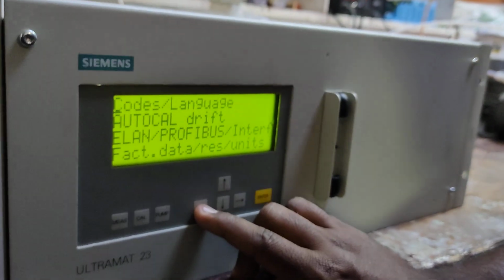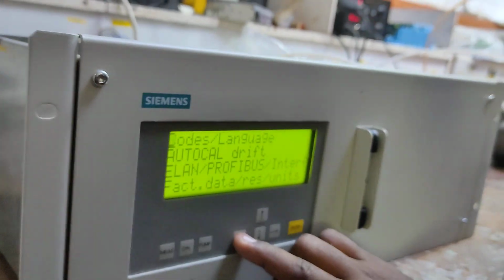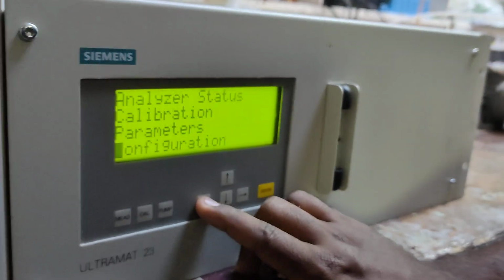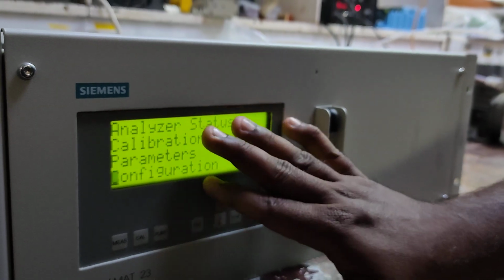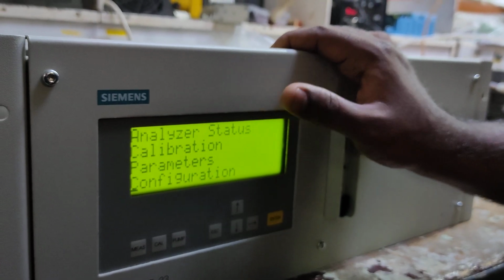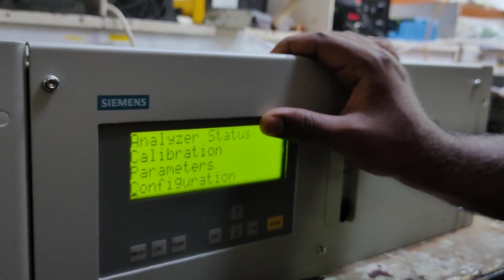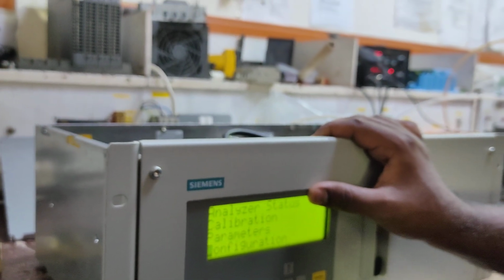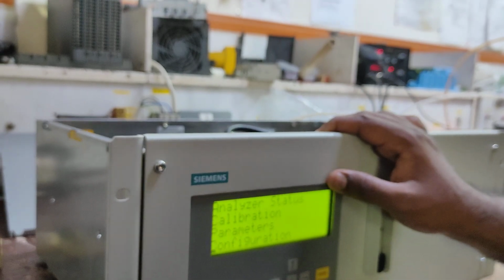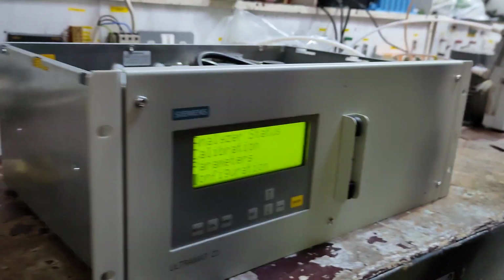A lot of alarms are there. All the alarms are in the manual. But what I am showing is your day-to-day routine, what you are doing, the main basic things. Now we have seen the major parameters: how to check the detector, how to check the O2 sensor, how to check the analog outputs, analog inputs, ranges, relays, etc. Now the last is the calibration. Just a second.